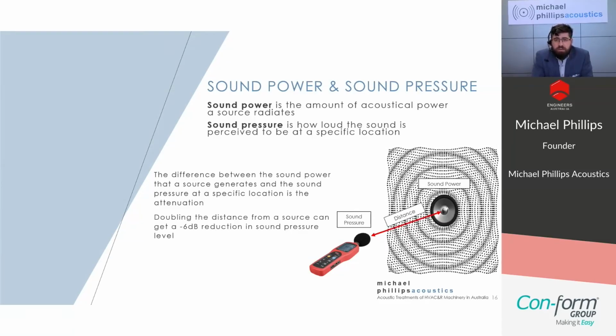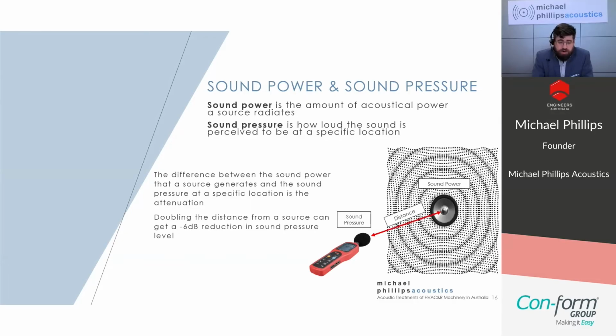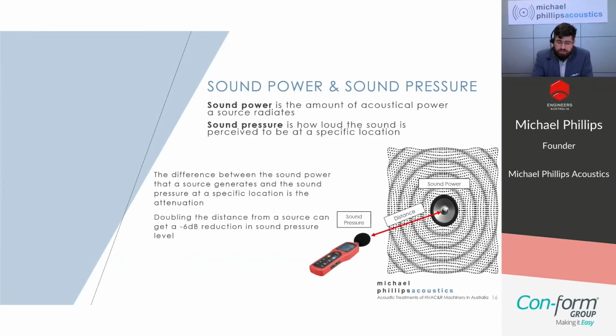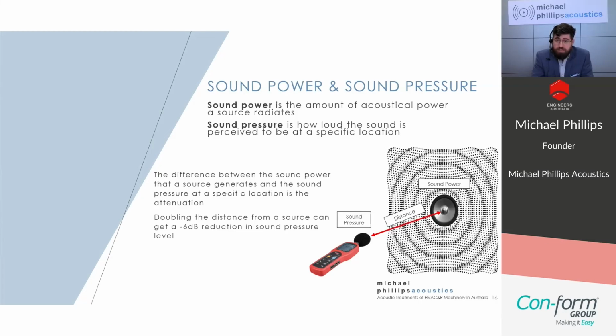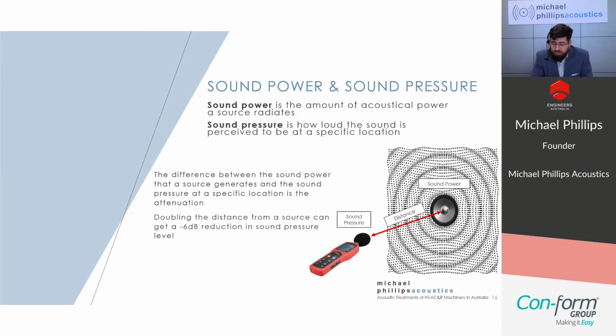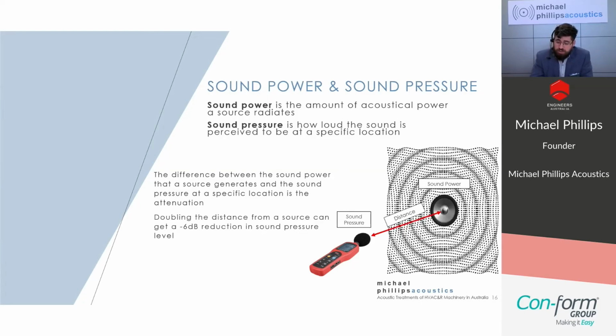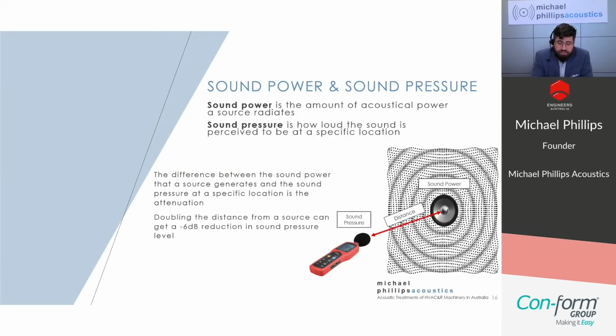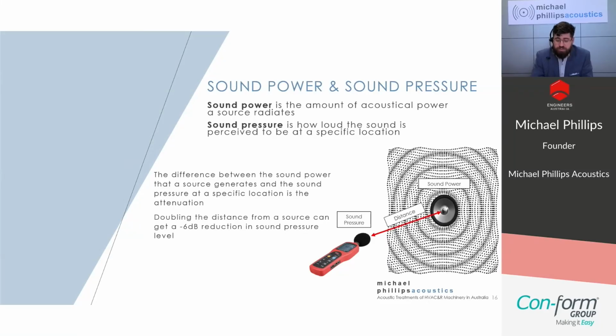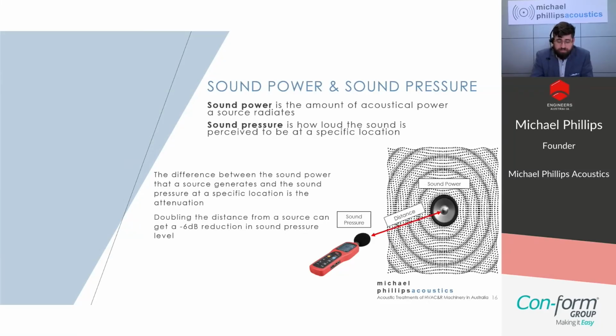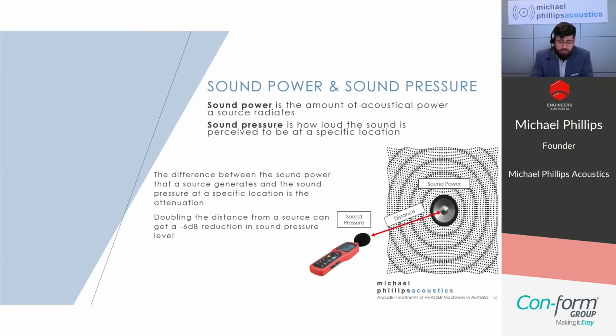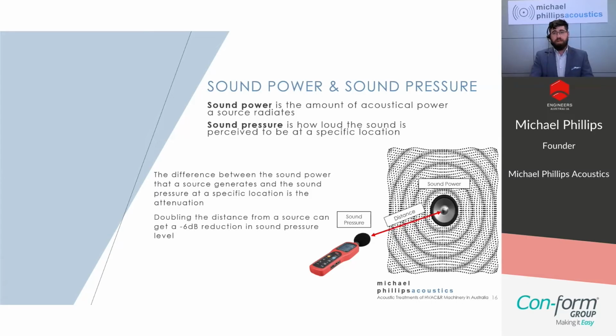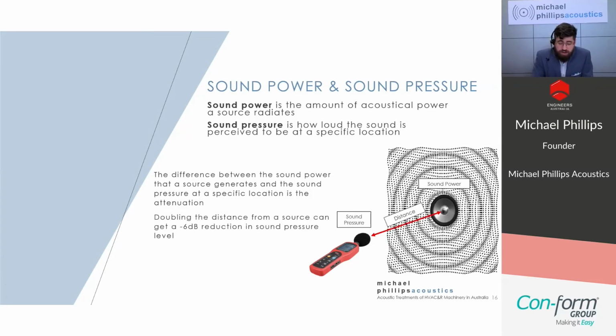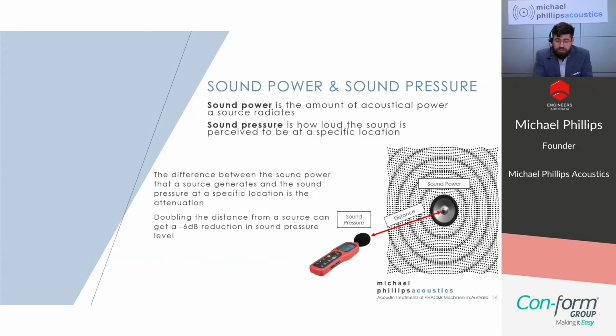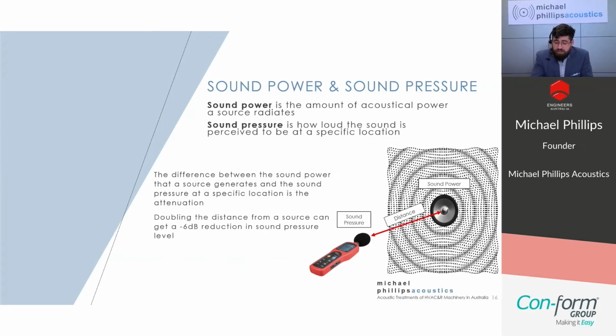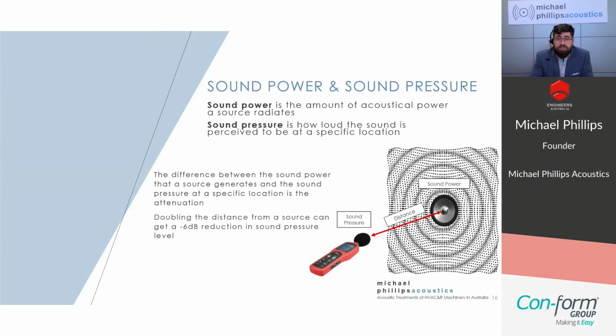When we're assessing for mechanical noise, it is much more useful to know the amount of sound power produced by a source than to know the sound pressure measured, as any measured sound pressures will factor in the environment. Constant sound power will produce different sound pressure levels when placed in different environments. So as a result, it's preferred to obtain sound power ratings of potential noise sources during the design stage. So we need to take this into account when calculating noise levels and specifying a solution.